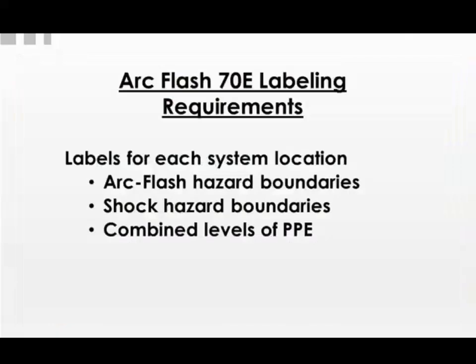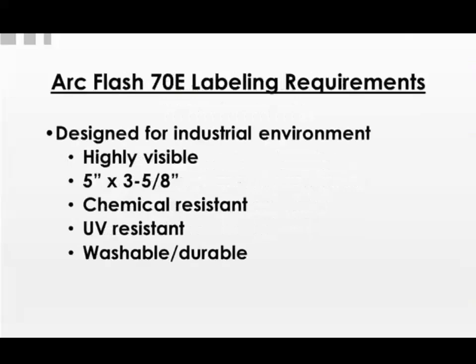Arc flash labeling requirements. You want to label each system location for the arc flash hazard boundaries, the shock hazard boundaries, and the combined levels of PPE. The labels are designed for industrial environments, so they should be sturdy, highly visible, 5 by 3 5/8 inches, chemical resistant, UV resistant, washable and durable. You don't want them fading or wearing off. And if they do, then they need to be replaced. That should be part of your arc flash program: once these labels are up, make sure that the labels are still legible and certainly that employees are following them.